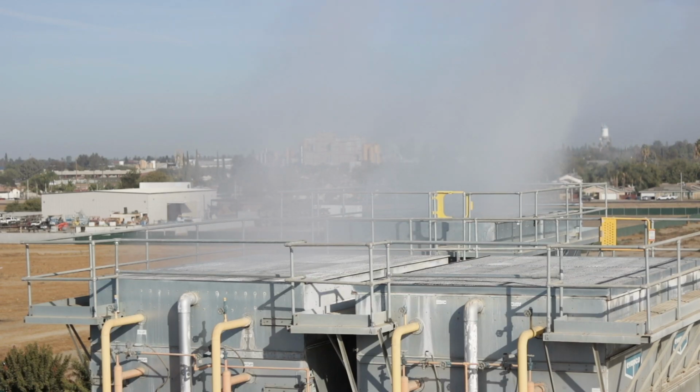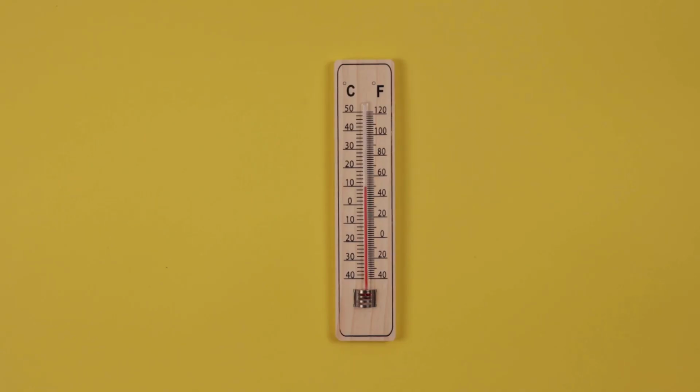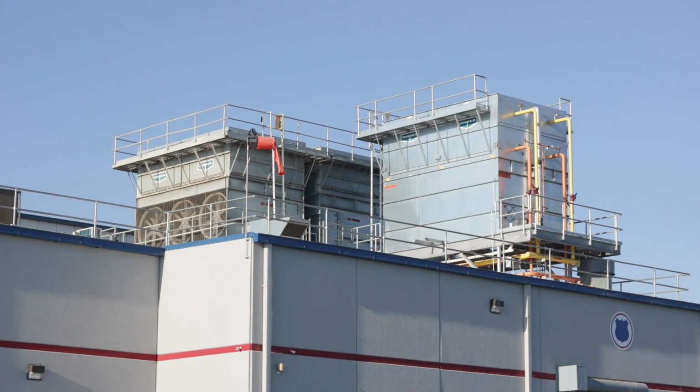Wet bulb temperature is an important concept to understand how some condensers leverage evaporative cooling to reject heat to the atmosphere. The wet bulb temperature is a measure of the lowest temperature that can be achieved through the evaporation of water into the air, assuming constant pressure. Put another way, wet bulb temperature includes the combined effect of temperature and humidity on the cooling potential of the air. It is a critical parameter in evaporative condenser and cooling tower design and operation.